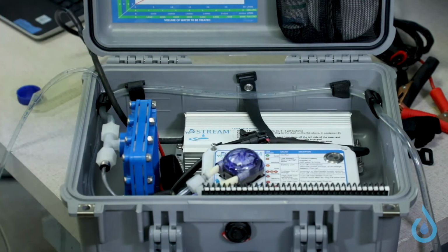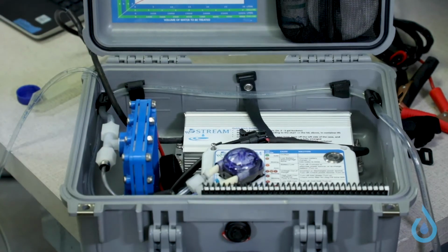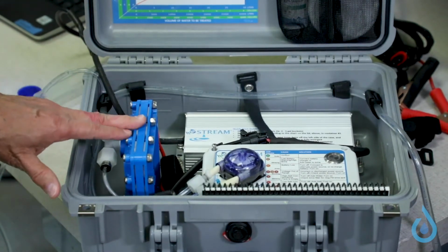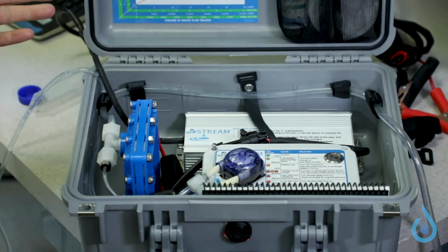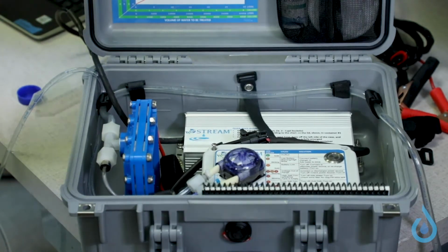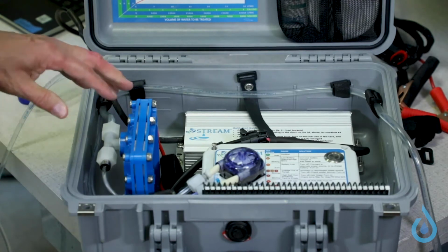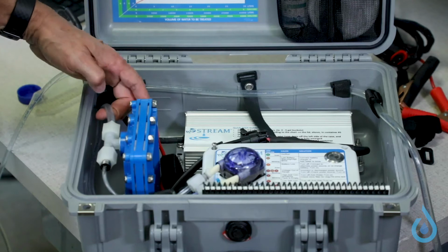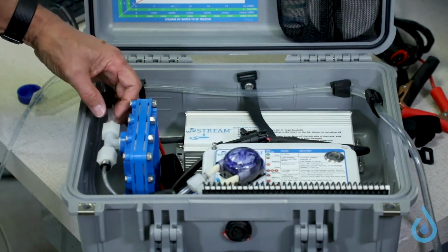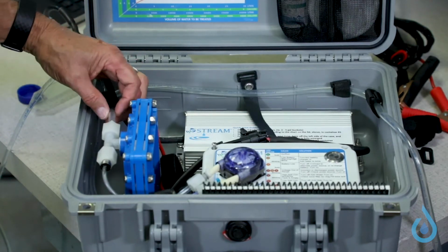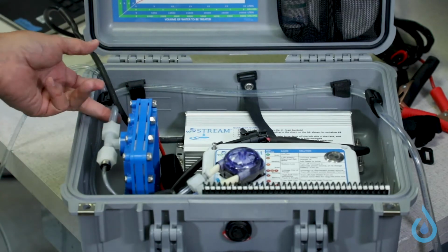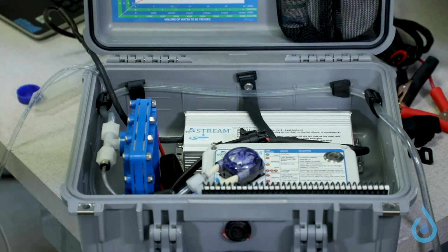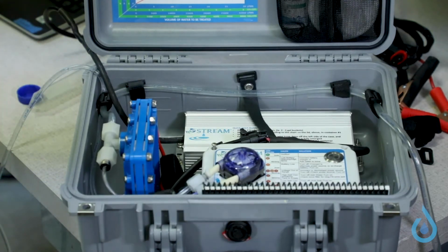Now the second major source of problems with this is that the flow in the cell is blocked. Now this occurs usually under only one condition, that is that scale has formed in the cell or in the fittings or in the tubing here. And you'll notice that the tubing is clear here, but when it begins to get blocked, it'll have a cream or white color inside the tubing. And that's a strong indication that scale is forming in the cell.